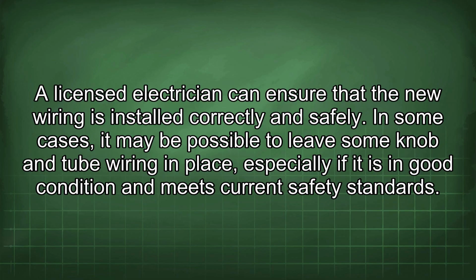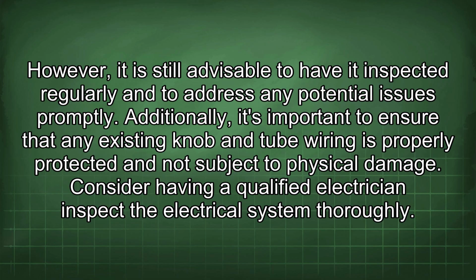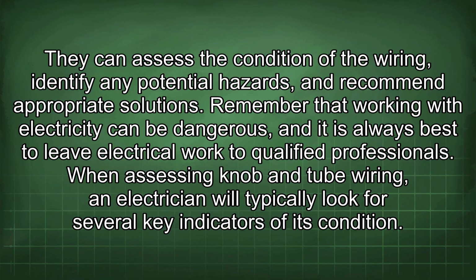In some cases, it may be possible to leave some knob and tube wiring in place, especially if it is in good condition and meets current safety standards. However, it is still advisable to have it inspected regularly and to address any potential issues promptly. Additionally, it's important to ensure that any existing knob and tube wiring is properly protected and not subject to physical damage. Consider having a qualified electrician inspect the electrical system thoroughly. They can assess the condition of the wiring, identify any potential hazards, and recommend appropriate solutions. Remember that working with electricity can be dangerous, and it is always best to leave electrical work to qualified professionals.